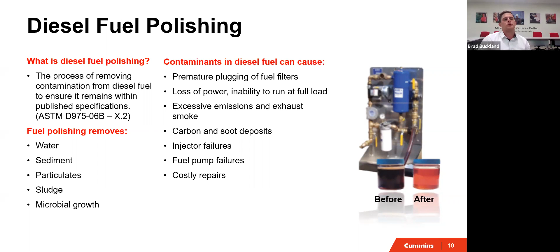It really cleans your fuel so you don't have to worry about any water that might be in there. Not touching it for 6 to 12 months is when we start to see issues, so if you're running a fuel analysis routinely every year, you really don't need to worry about your fuel being dirty. But if you're not checking it every 6 to 12 months, and the tank isn't above 75% full, which is our recommendation at minimum, that matters. You want enough fuel to keep going through any emergency, and if these are outside tanks, you're not dealing with as much moisture. At 75% or plus full, there's just a little bit less room for air.